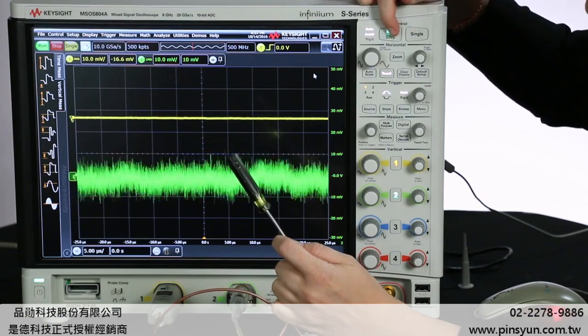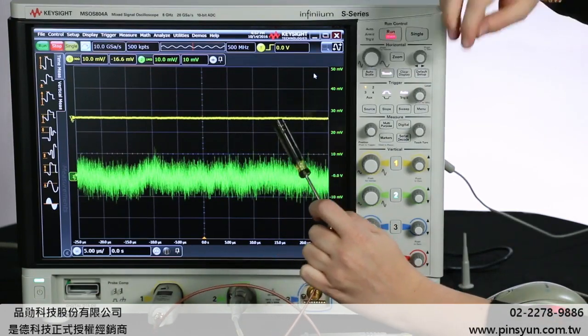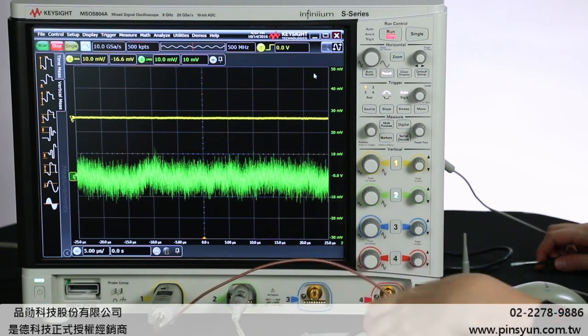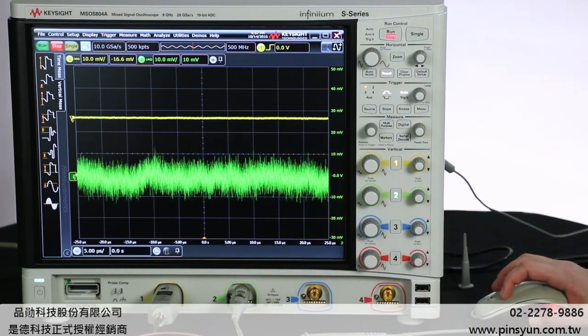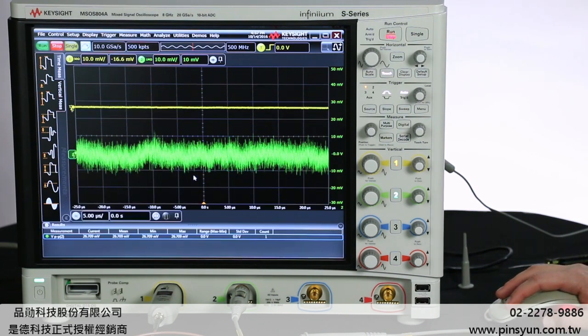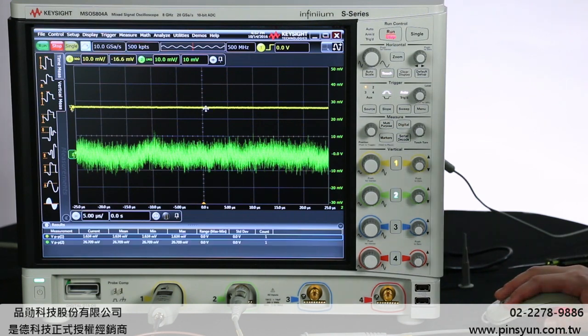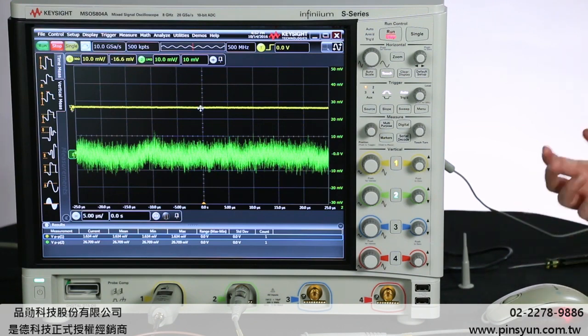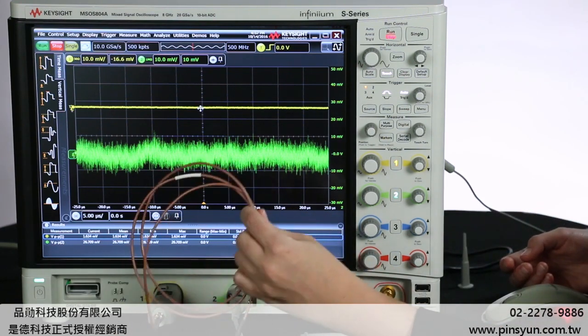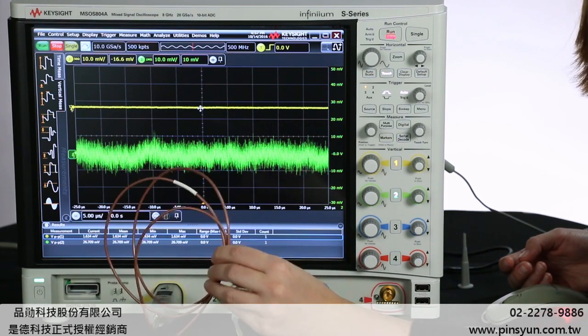And to free up my hands, I'm going to just go ahead and stop the acquisition. And now we've captured that measurement, so let's take a voltage measurement on each of these. So on channel 2, on the passive probe, it looks like 26.7 millivolts of baseline noise. And on my active probe, I've got 1.6 millivolts of baseline noise. So that's about 20 times less noise on this power rail probe than on your standard passive probe.